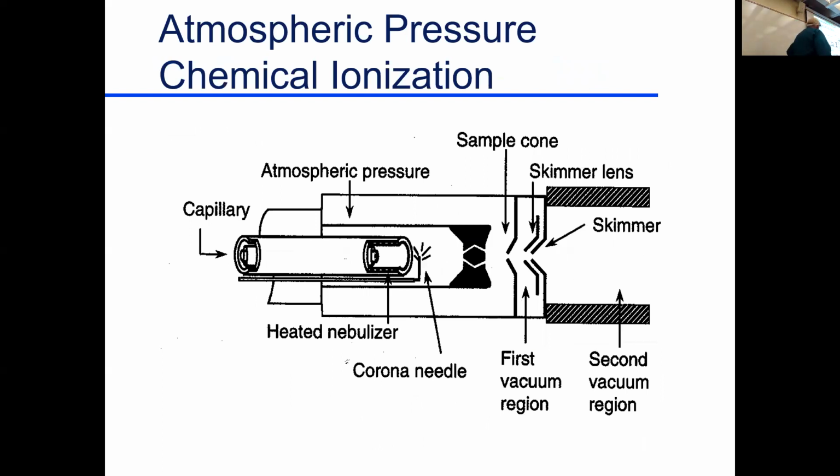Atmospheric pressure chemical ionization is actually a somewhat similar system. I'm going to show you an application of this a little bit later on. But here's your capillary tube, and this can come from the air. It can be in a balloon riding up in the sky, monitoring pollution. It can be almost any place. So you're going to be drawing in actually an atmosphere of some kind. Then it comes drawn into the system. There's now a corona discharge needle here that's again a few thousand volts. And so you put an electrical charge again on anything that's coming through this inlet system.